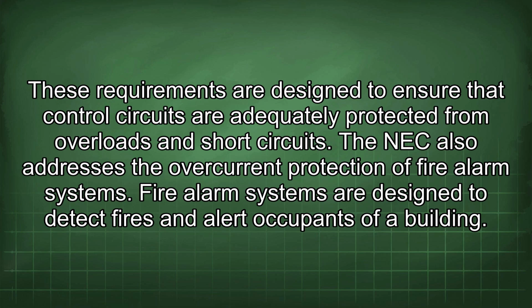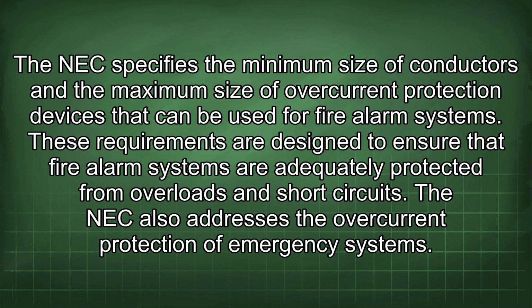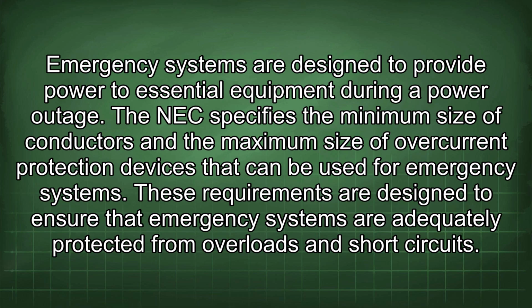The NEC also addresses the overcurrent protection of fire alarm systems. Fire alarm systems are designed to detect fires and alert occupants of a building. The NEC specifies the minimum size of conductors and the maximum size of overcurrent protection devices that can be used for fire alarm systems. These requirements are designed to ensure that fire alarm systems are adequately protected from overloads and short circuits. The NEC also addresses the overcurrent protection of emergency systems. Emergency systems are designed to provide power to essential equipment during a power outage. The NEC specifies the minimum size of conductors and the maximum size of overcurrent protection devices that can be used for emergency systems. These requirements are designed to ensure that emergency systems are adequately protected from overloads and short circuits.